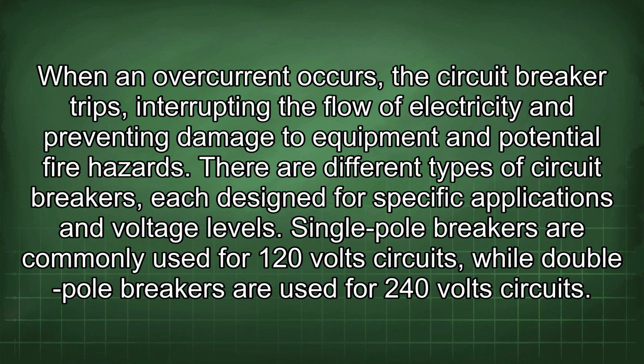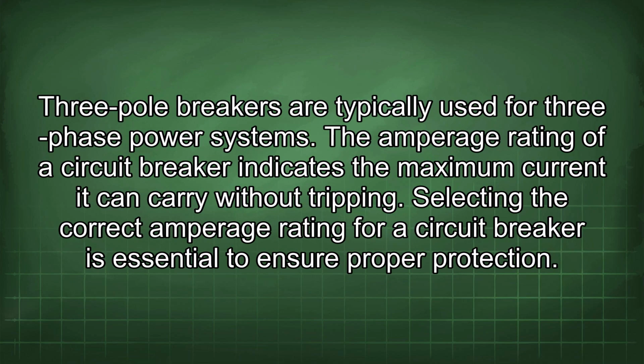There are different types of circuit breakers, each designed for specific applications and voltage levels. Single-pole breakers are commonly used for 120-volt circuits, while double-pole breakers are used for 240-volt circuits. Three-pole breakers are typically used for three-phase power systems.